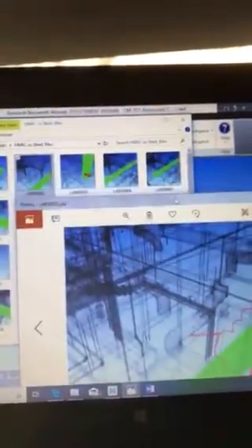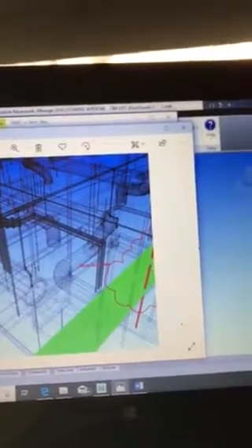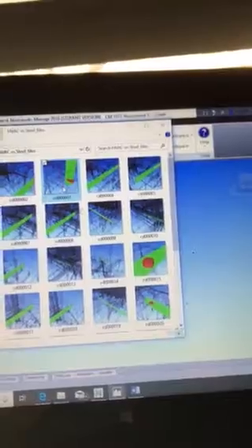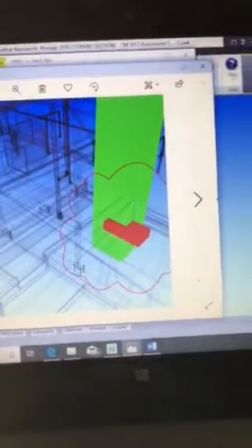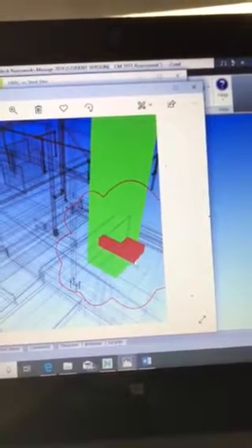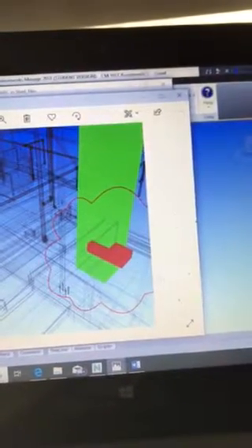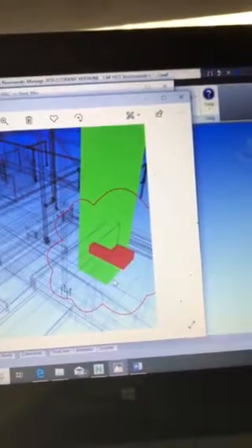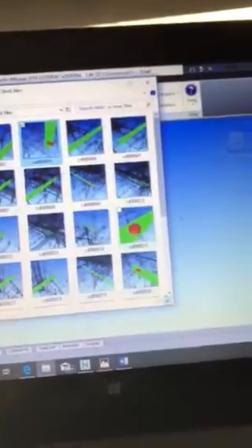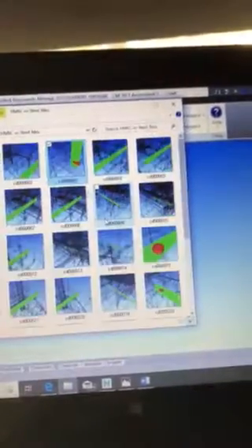This is for the HVAC system and the structural steel. Here we have a duct interfering with the structural steel. We also have this one on this side, on this viewpoint that I saved. For this, we could have the engineers set up a game plan and adjust this one. They can move it either coming this way or adjust it the other way, something that will not affect the walls when they're coming in. I had about 20-something clashes on this one.